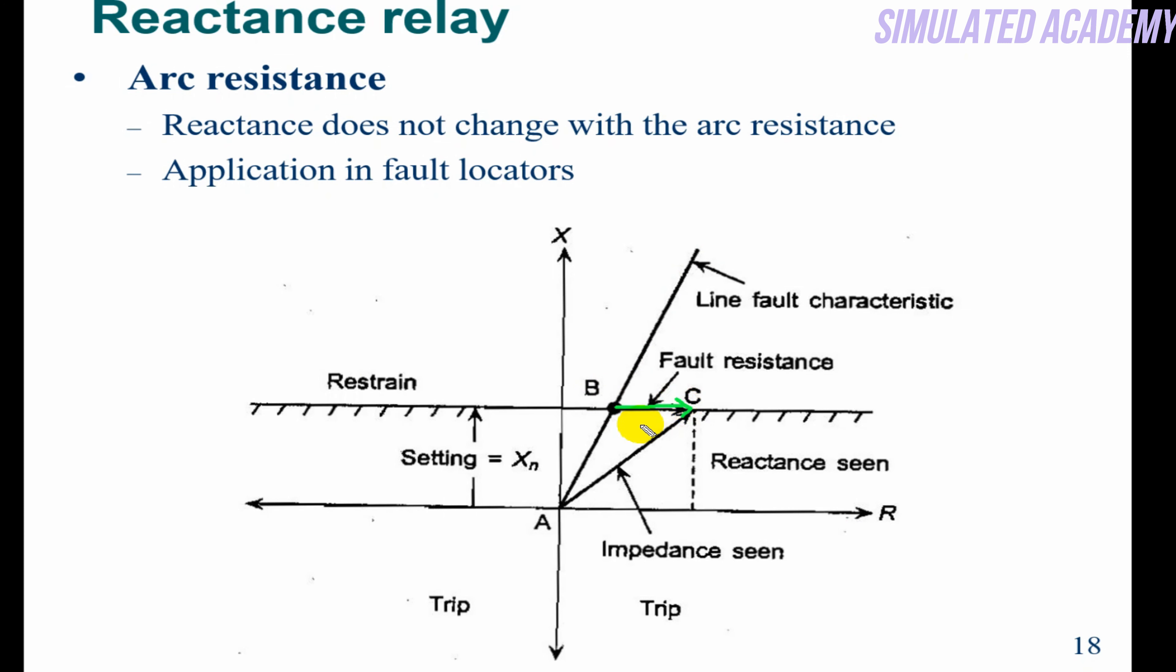If arc occurs, because of the arc it will shift this way. So what does this mean? This means that reactance doesn't change with arc resistance. Arc resistance is the real part, so it changes this way; reactance changes this way.